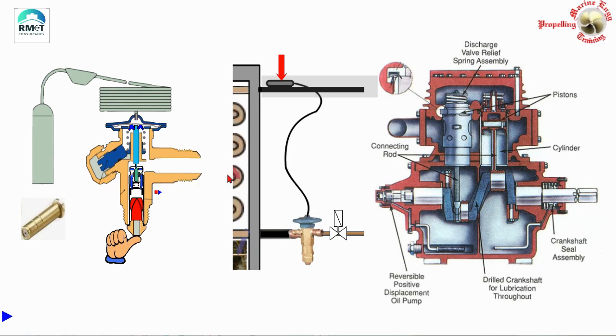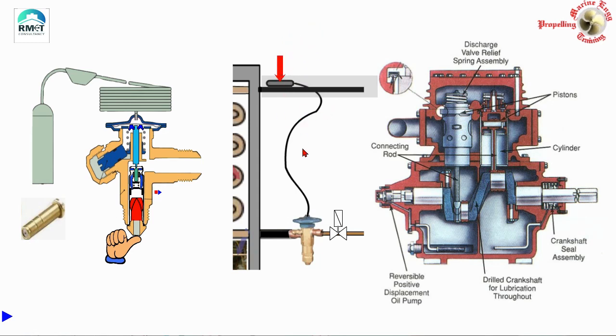Having understood all this, you will realize the importance of the bulb picking up the exact temperature of the gas leaving the evaporator. If you have not ensured that the bulb is touching the pipe properly, or there is debris between the bulb and the pipe, or it is not clamped properly, or the insulation is not good enough and heat from the room is affecting the bulb, then the temperature sensed by the bulb will not reflect the actual superheated gas temperature — it may be much higher. We must ensure that the bulb is, as far as possible, at the same temperature as the gas leaving the evaporator.